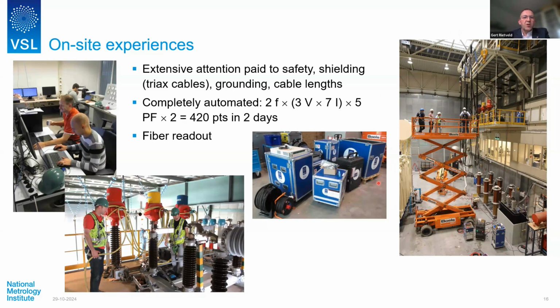So our voltage measurement is using triaxial cables in order to really shield all unwanted influences, and also not to be sensitive to ground loops and grounding, because in such an industrial laboratory, you will not have a common, well-defined ground. The ground in one corner of the lab is really different, at the ppm level that we are measuring, than at another location. So grounding is extremely important. It's one sentence here, but it's actually maybe even more than a year of work to find out all the details that are relevant to get ppm accuracy in an on-site measurement. So far from trivial. I already mentioned the automation. With our present system, we can really cover a lot of voltage, current, and power factor combinations, more than 400 points in roughly 2 days.